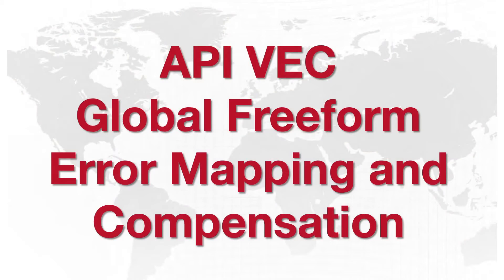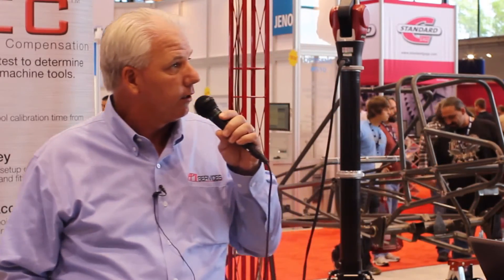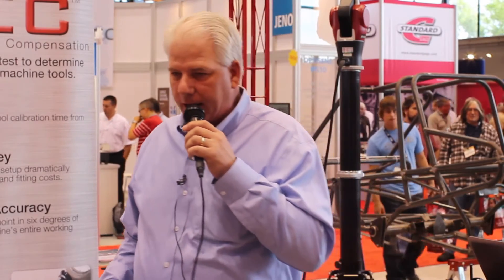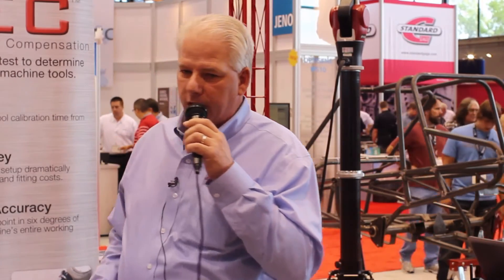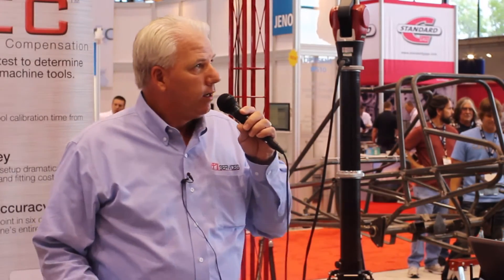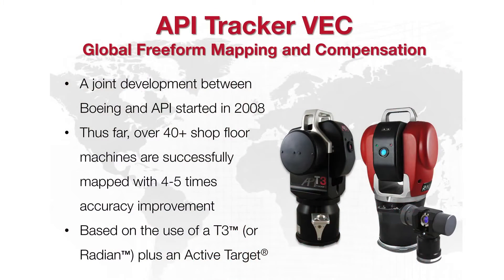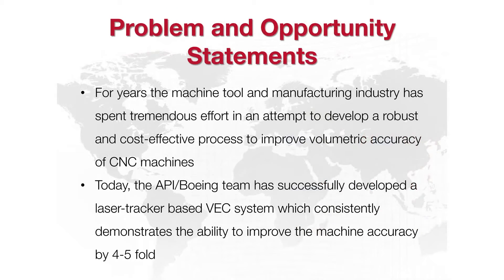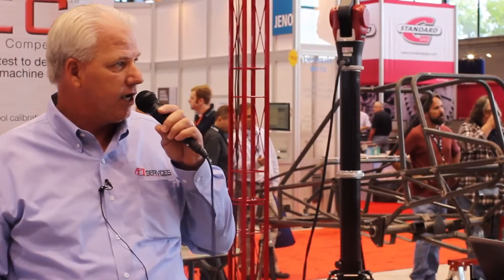The API VEC Global Freeform Error Mapping and Compensation is our latest volumetric package. Freeform means asymmetrical — we collect data on a point cloud, very randomly throughout the volume, utilizing all five axes. VEC was developed as a joint process between Boeing and API back in 2008, and we've done 40-plus machines with calibration improvements of four to five times.